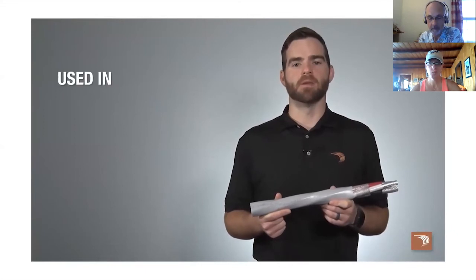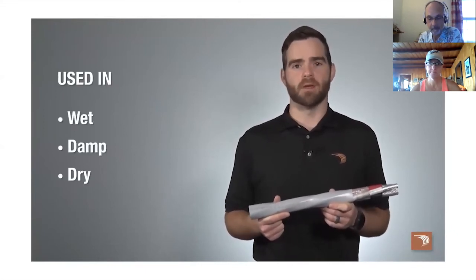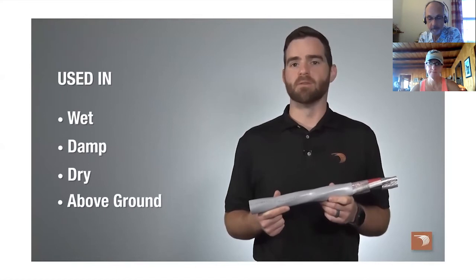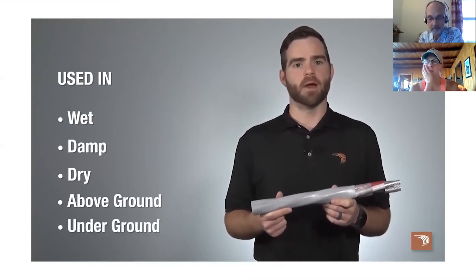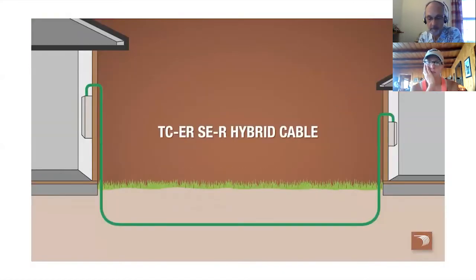Tray cable SER hybrid cable can be used in wet, damp, and dry locations, as well as above ground in direct UV sunlight or underground for direct burial applications. With this one hybrid cable, it can seamlessly convert from indoor using its type SER rating to outdoor and then directly into the earth using its tray cable direct burial ratings. There's no need for a junction box or cost of transitions. When necessary to transition outside underground into a building, such as a detached building or structure, or to a remote piece of electrical equipment, the tray cable SER hybrid cable streamlines the installation process.